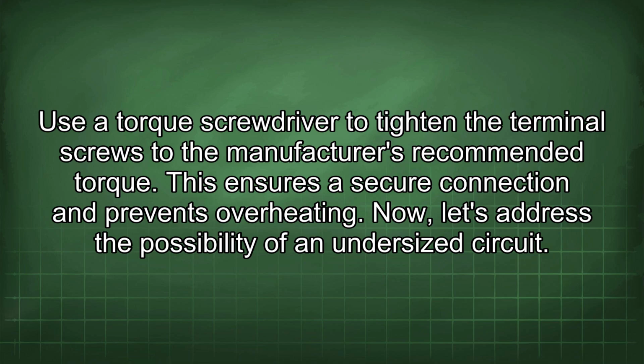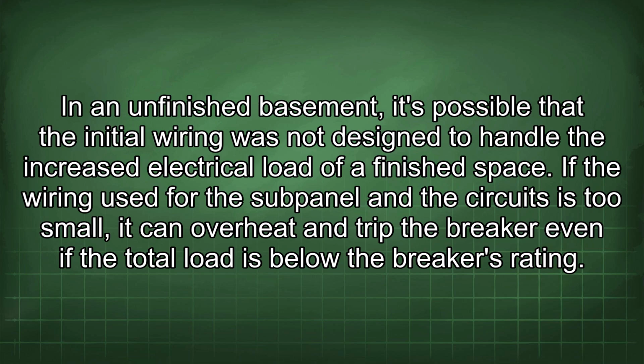Now, let's address the possibility of an undersized circuit. In an unfinished basement, it's possible that the initial wiring was not designed to handle the increased electrical load of a finished space. If the wiring you use for the subpanel and the circuits is too small, it can overheat and trip the breaker even if the total load is below the breaker's rating.